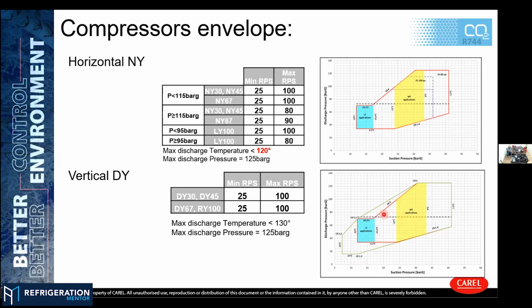This line means subcritical or transcritical. For the subcritical zone, we can operate both MT and LT. And for the transcritical zone, we can operate as transcritical or as parallel. If we need a transcritical low temp condensing unit, we can have two compressors, one with low temp application and the second one as parallel, just to make sure that we can maximize the efficiency of the unit, so having the better COP.